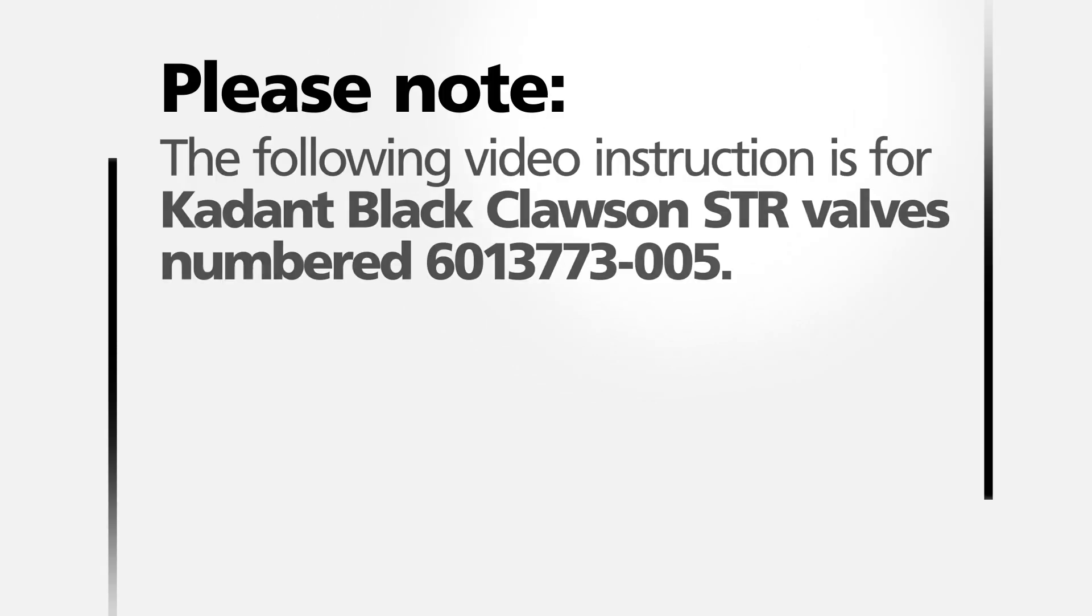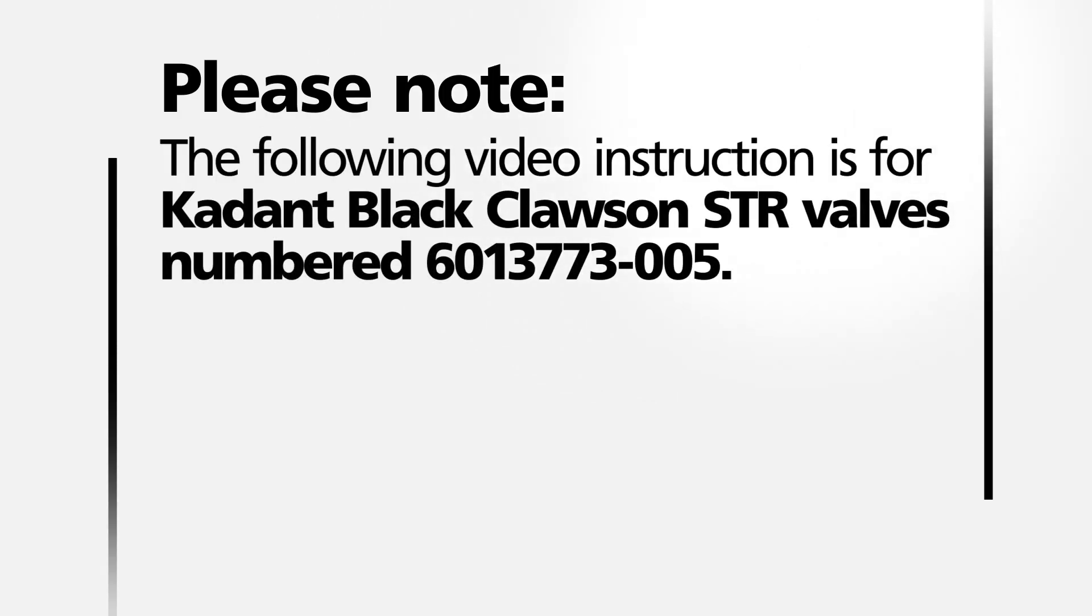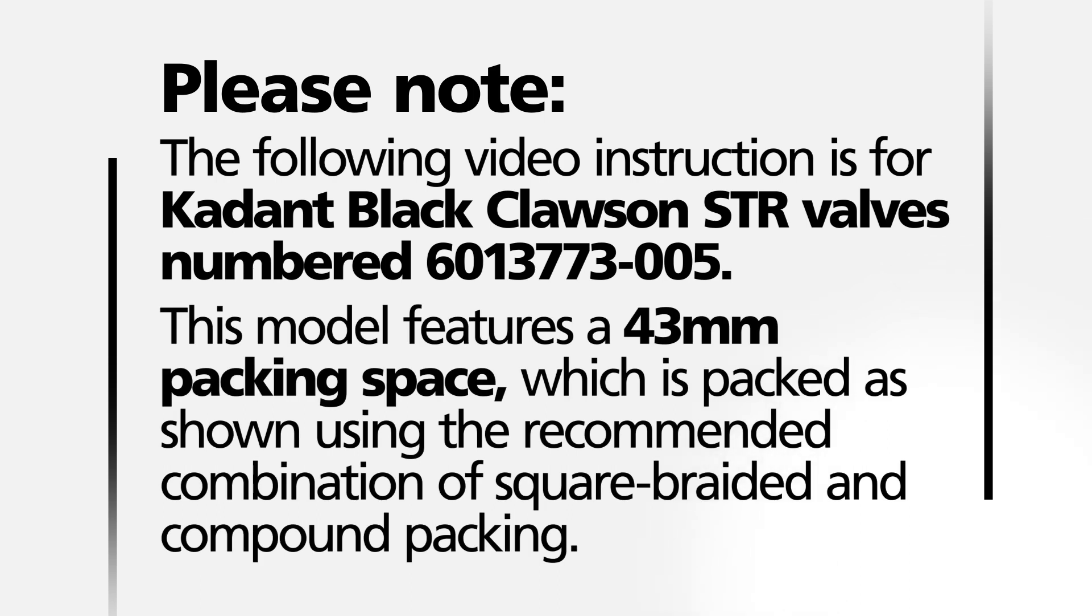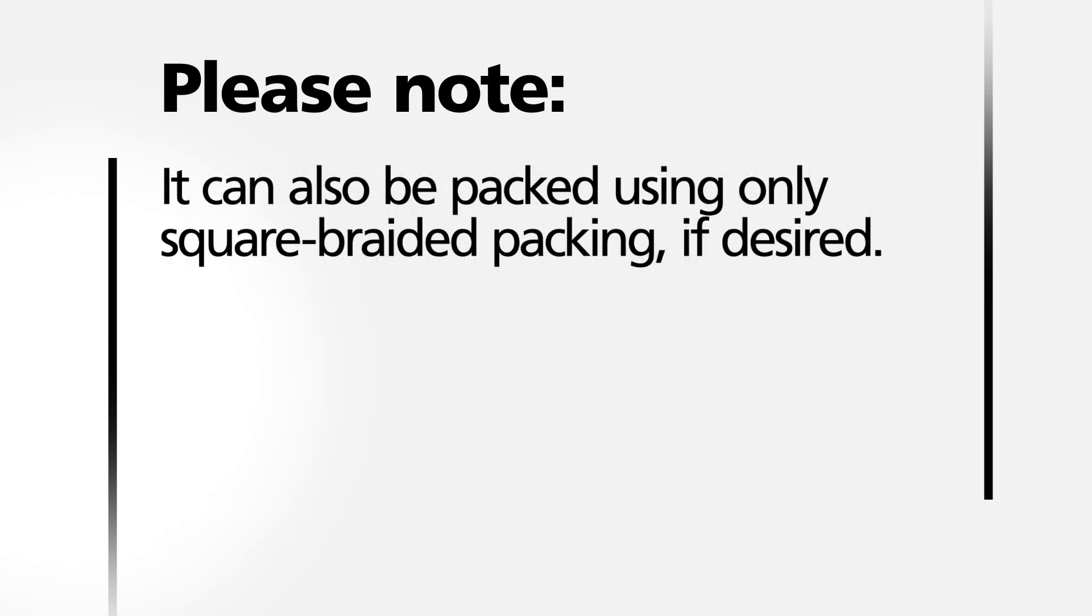The following video instruction is for Kadant Black Clawson STR valves numbered 6013773-005. This model features a 43mm packing space which is packed as shown using the recommended combination of square braided and compound packing. It can also be packed using only square braided packing if desired.